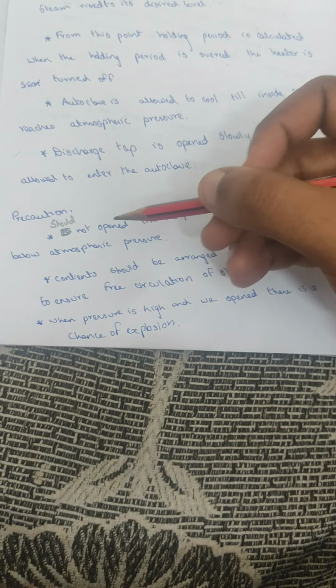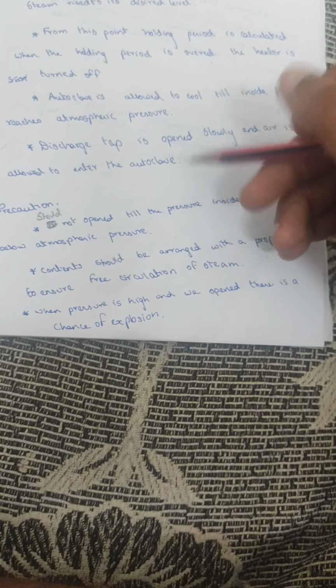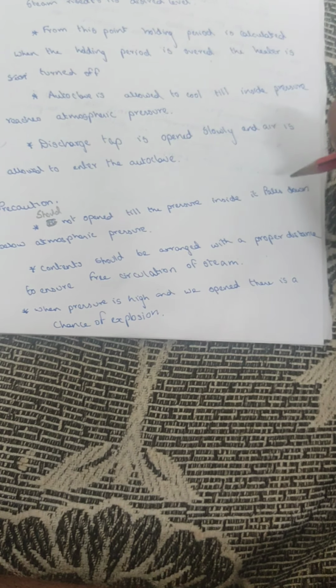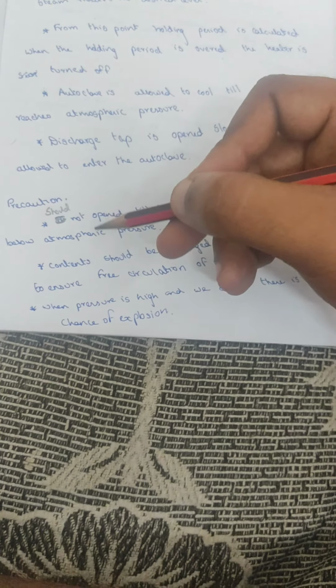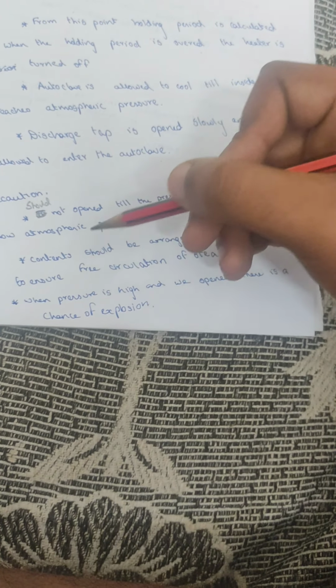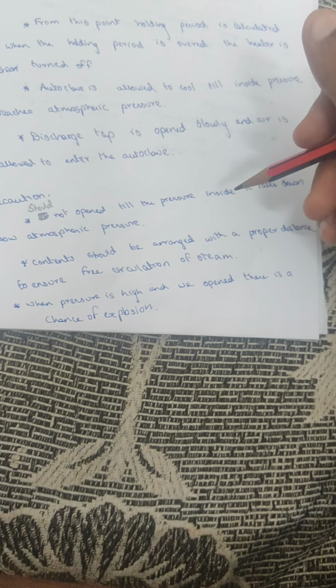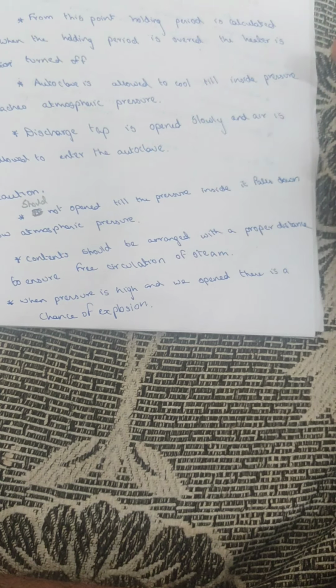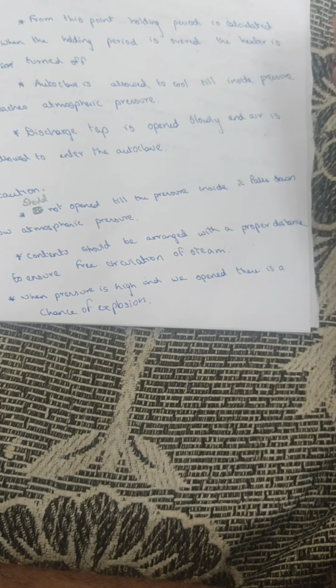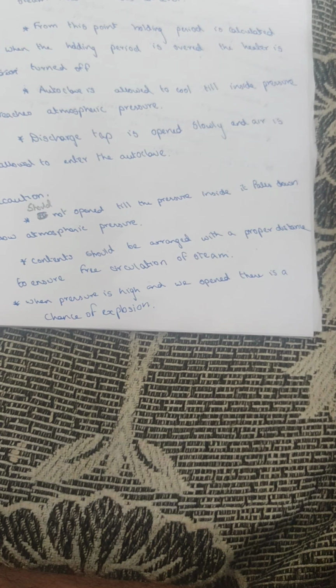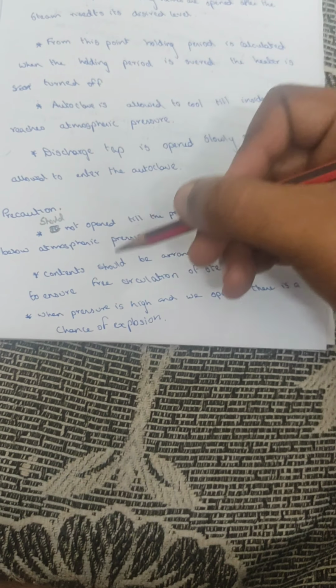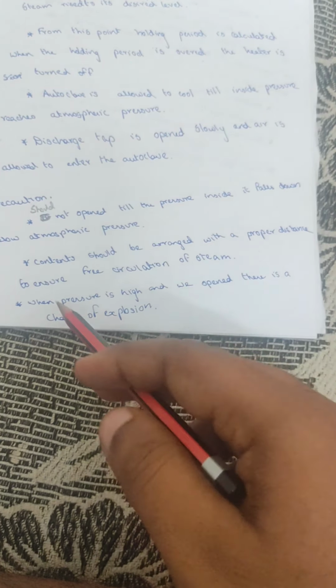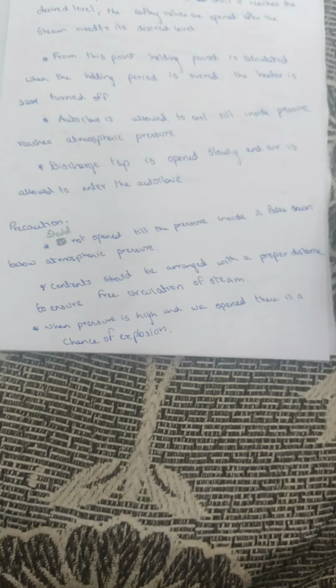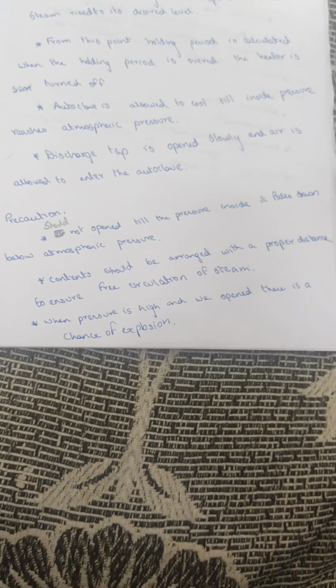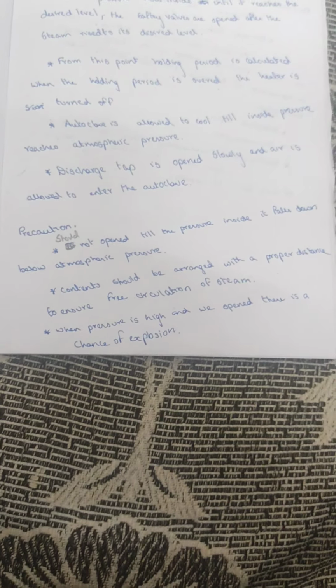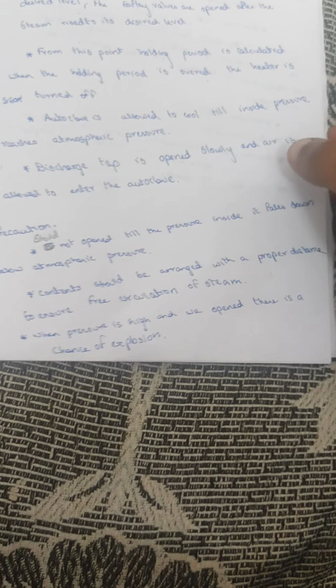Precautions to be followed: we should not open the autoclave until the pressure inside it falls down to atmospheric pressure. Contents should be arranged at a proper distance to ensure free circulation of the steam. The contents inside the autoclave should be adjusted, leaving gaps in between them to allow the steam to circulate freely. If we open when the pressure is high, there is a chance of explosion. We should open only when the pressure comes down to the atmospheric level. Before that, there is a chance of explosion.